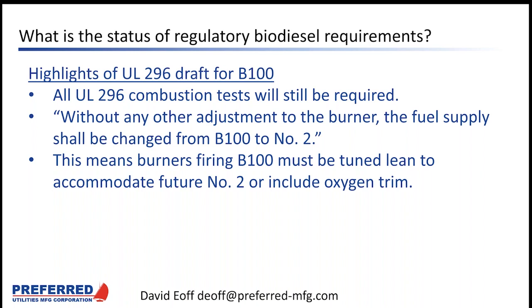In the event there is a severe supply chain disruption in the production of, or delivery of biodiesel, there aren't going to be enough burner technicians to give everyone switching to diesel a retune. So my interpretation of this is that the burners must be tuned lean on biodiesel so that they don't smoke when firing diesel, or they have to have a control system that can automatically accommodate burning both fuels. This question comes up every time I talk to facility people about burning biodiesel in their boilers. They don't want to be stuck burning biodiesel in case they can't get a delivery. They want to make sure they can always go back to firing number 2 oil in the event biodiesel isn't available.